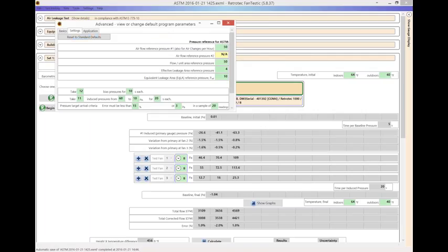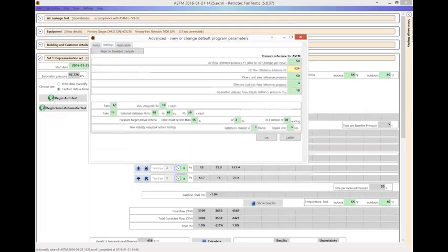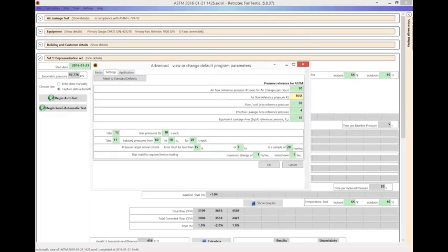The other is if something's going to open up in your building, you find out right away that, oh, a door blew open and so on, and you don't wreck the test. So you find out on the very first test point that all your windows and doors are closed properly, nothing's going to pop itself open.